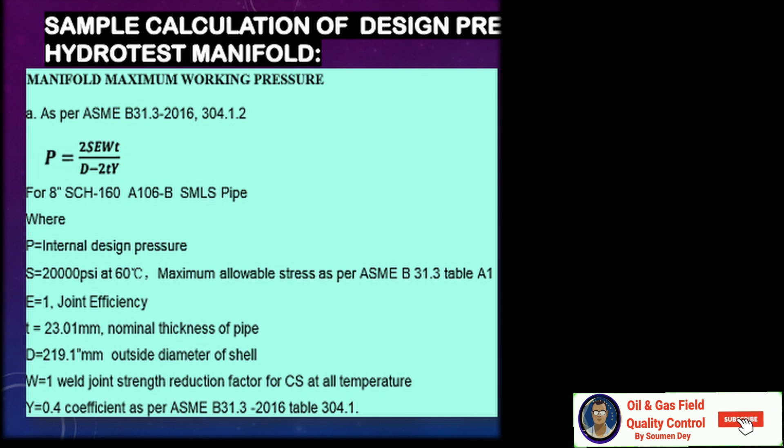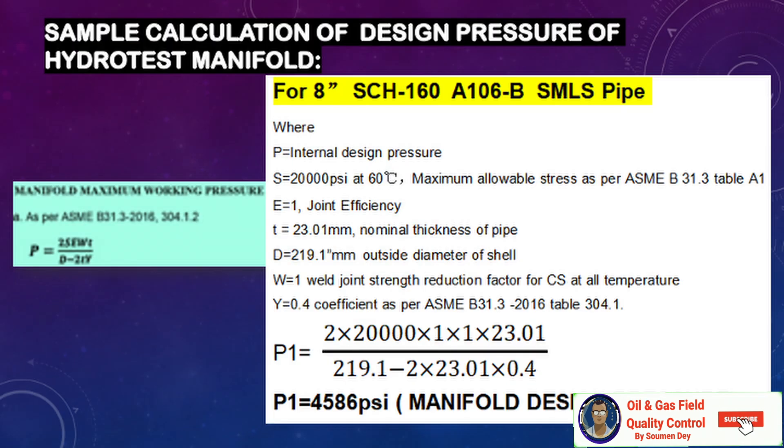The formula as per ASME B31.3 para 304.1.2 is: P = 2·S·E·W·t / (D − 2·t·Y). For an 8-inch schedule 160 pipe, Grade B: S = 20,000 psi (maximum allowable stress per B31.3 Table A-1), E1 is joint efficiency, t = 23.01 mm, D = 219.1 mm, W = 1 (weld joint strength factor), and Y = 0.4 (coefficient per B31.3 2016 Table 304.1). Putting all values in, the maximum design pressure for this 8-inch schedule 160 A106 Grade B pipe is 4,586 psi.